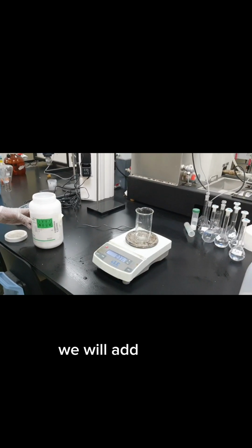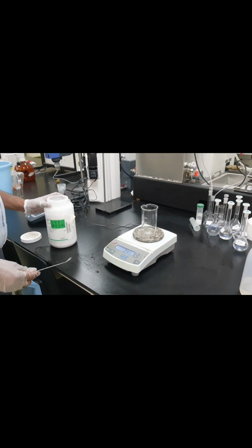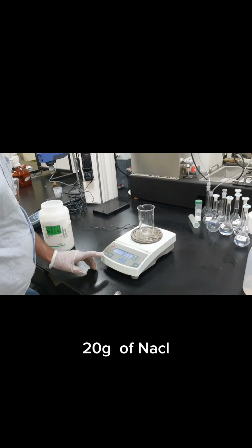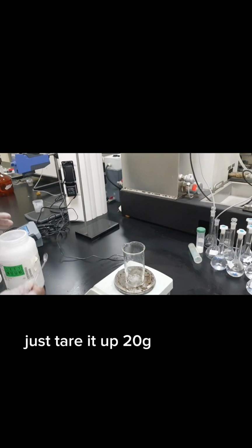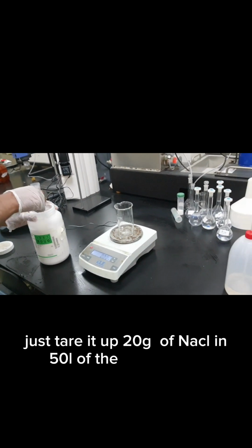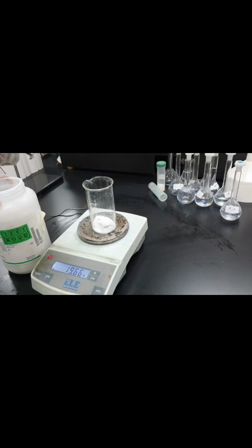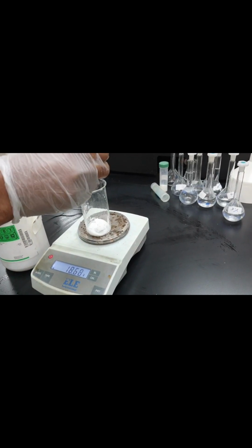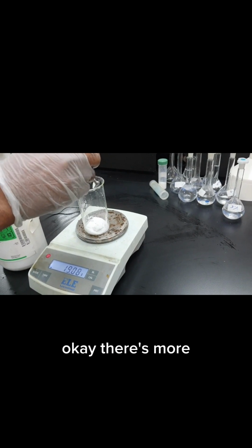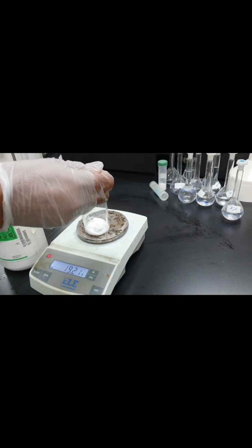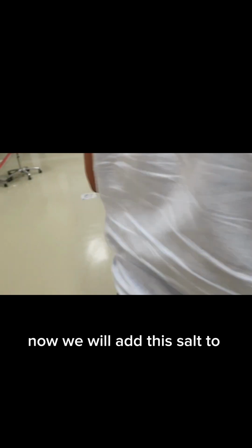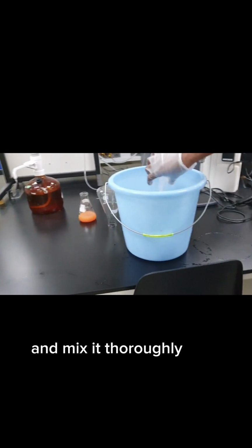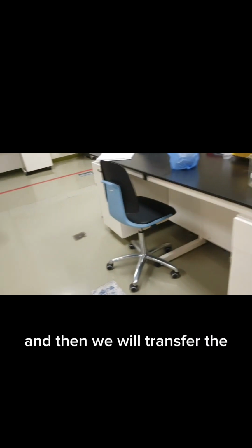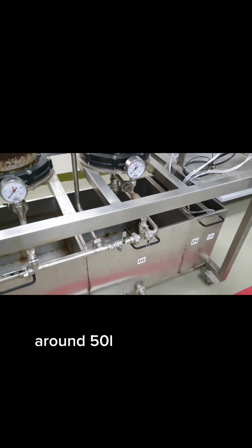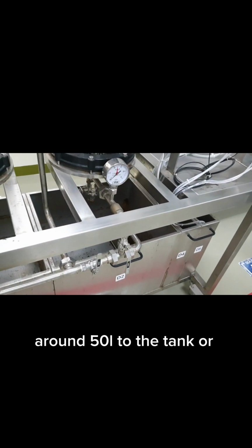So now guys, we will add around 20 gram of NaCl, and just stir it up. 20 gram of NaCl in 50 liters of water. This is a little more, just a pinch. Now we will add this salt to this bucket and mix it thoroughly, and then we will transfer the water, around 50 liters, to the raw water tank.